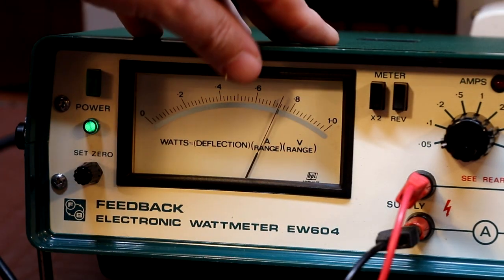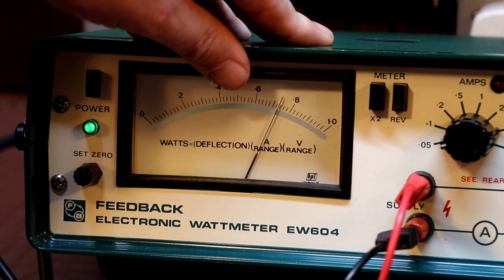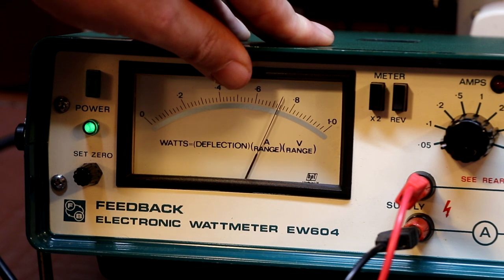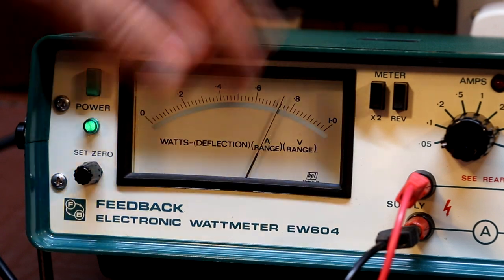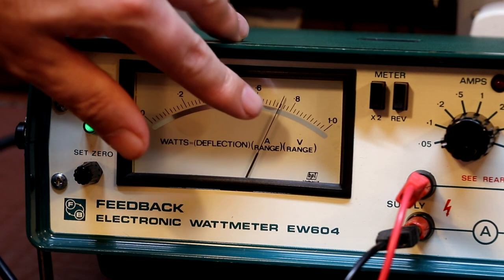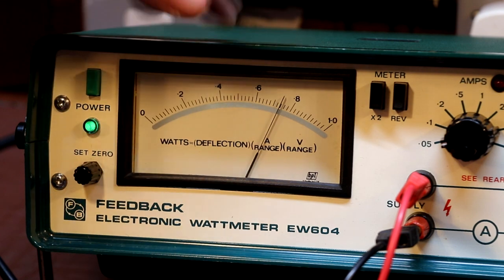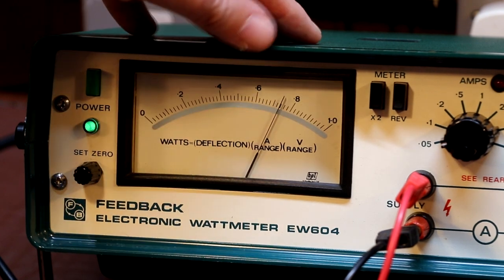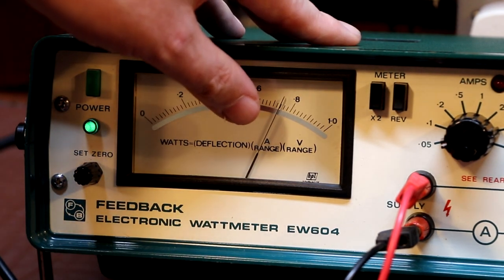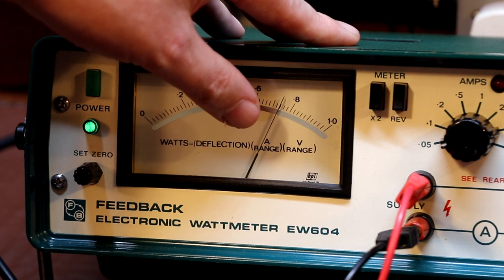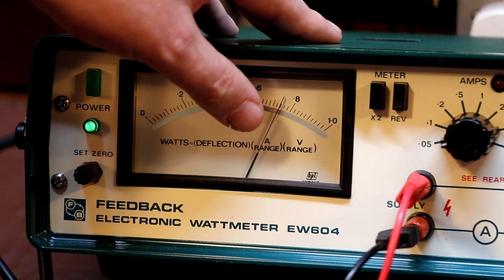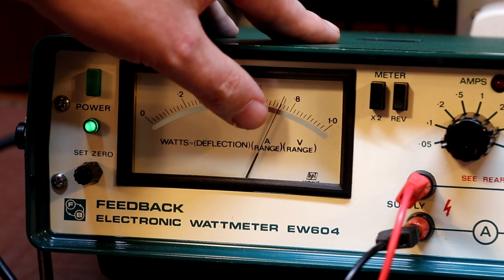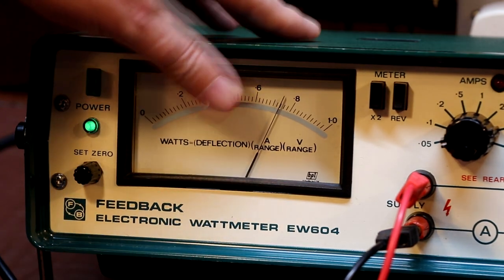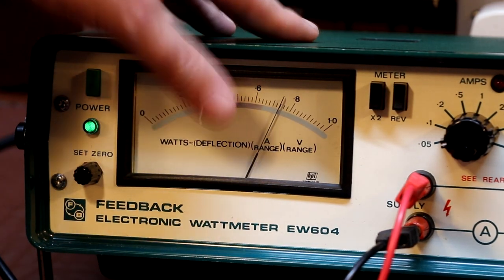And taking a look at our watt meter reading here, I can see that it's about 7.4 watts. So we're delivering 7.4 watts of power to our transformer. The needle is just bouncing around very slightly, and the reason it's bouncing around is because the supply voltage to my whole house is just varying a little bit. It's going up and down, so that means the amount of power being delivered to the transformer varies as well. But it is pretty much 7.4 watts at the moment.